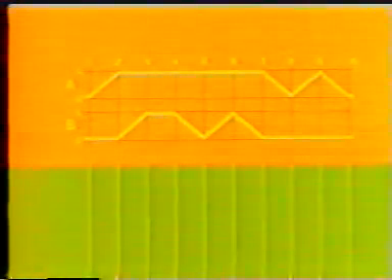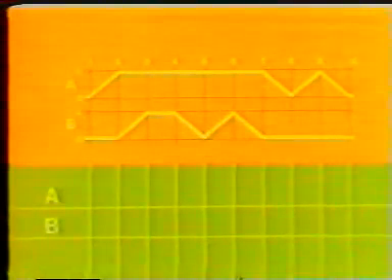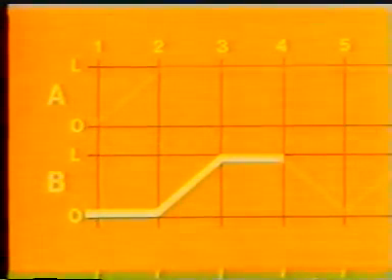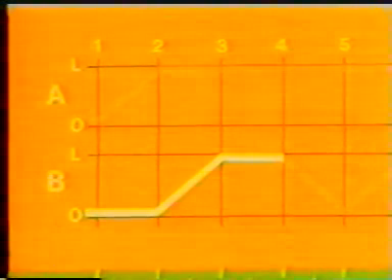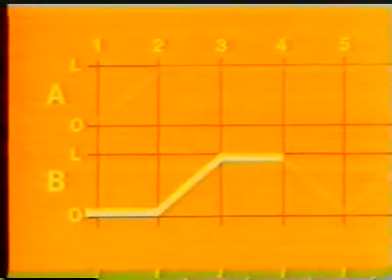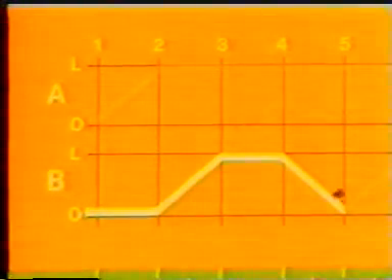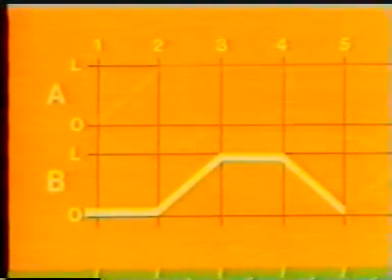Programming of the punched card is performed step by step, the necessary outputs being entered one beneath the other. If in the diagram a change takes place from O to L, a hole must be made in the card. If signal L is to be retained, the card is also punched. If the signal changes from L to O, or if the O signal is to be retained, no hole may be punched.